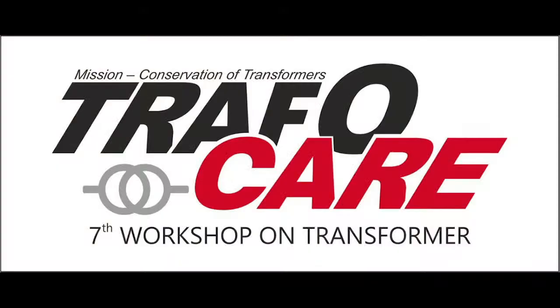During that moment, you should ask your transformer manufacturer whether the corresponding BIL insulation has been provided in the design of that particular winding at the neutral end. If it has been provided, then it's the way to go to have the NGR, if I am correct. Jayasanand sir can add to it, because he is the transformer manufacturer.